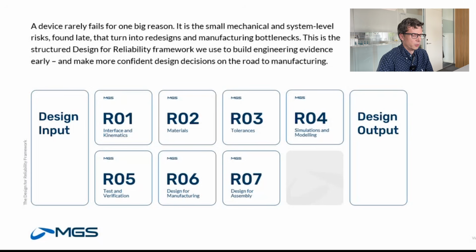When you do tolerance assessment, it's not just about treating all tolerance assessments equal, but it's about knowing where the risks are. Some tolerance assessments will see a gradual degradation of the device function, while for others you will see an abrupt failure. So you should never treat them equally.